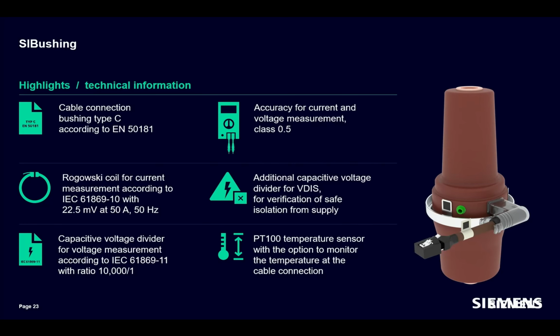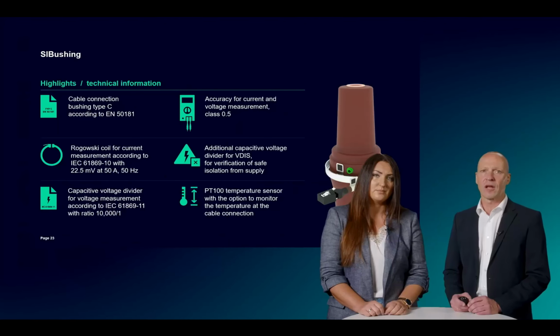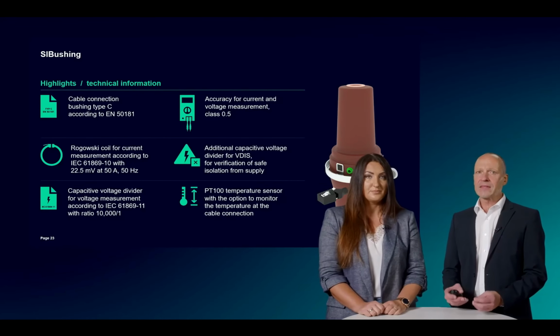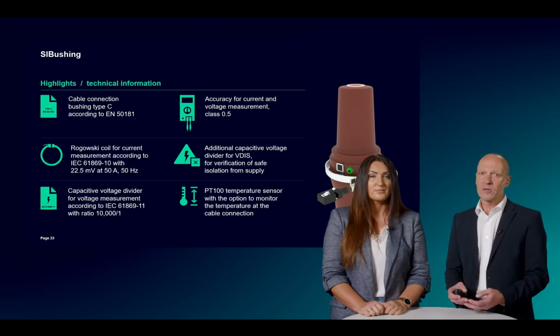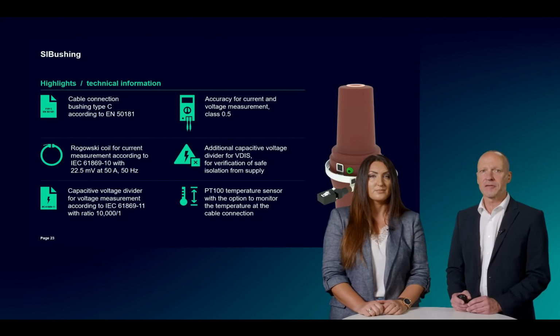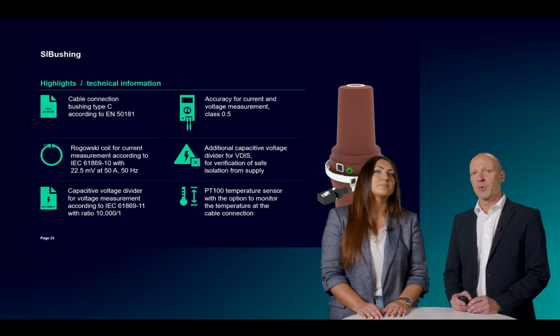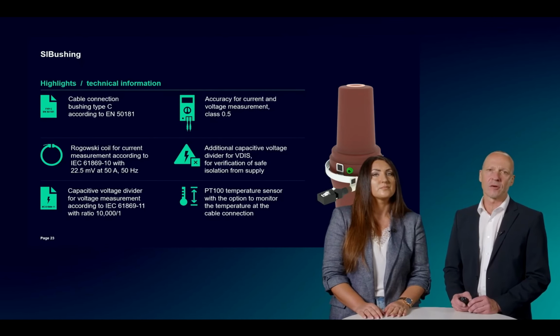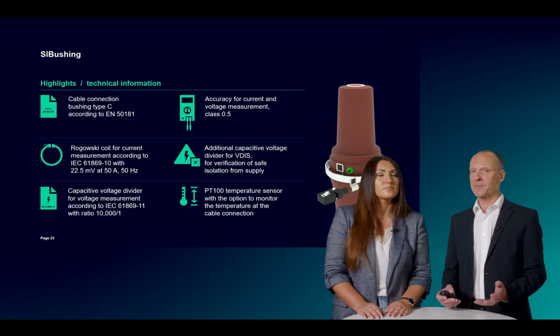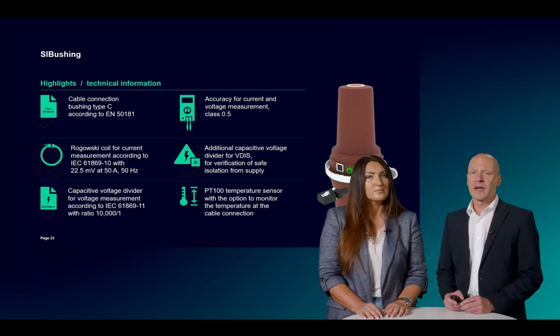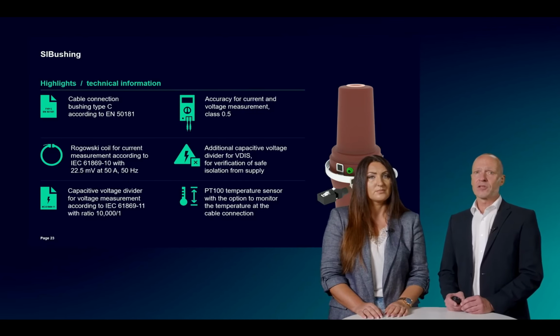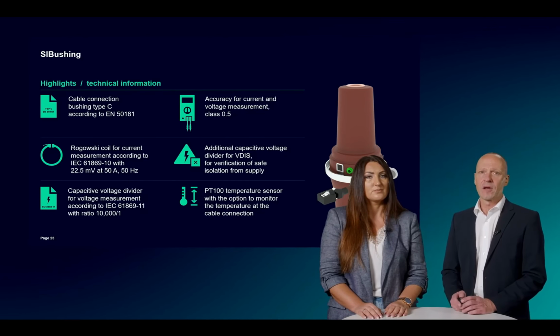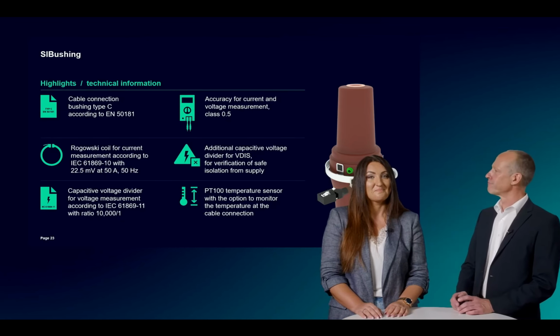We have an additional temperature sensor integrated, which is on the one hand used for compensating the voltage accuracy along the whole temperature range of -40 degrees up to +115 degrees. And this sensor can secondly also be used for further supervision of the cable connection to detect abnormalities caused by incorrectly installed cable plugs. And last but not least, we have the standard VDIS voltage divider integrated, which is used for verification of the absence or presence of the voltage.